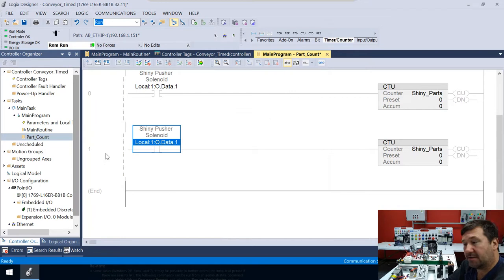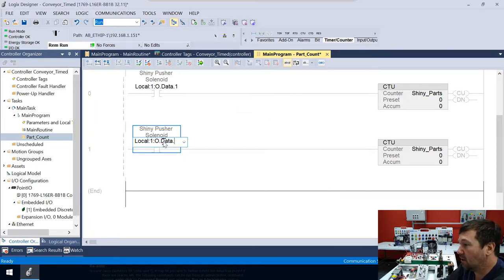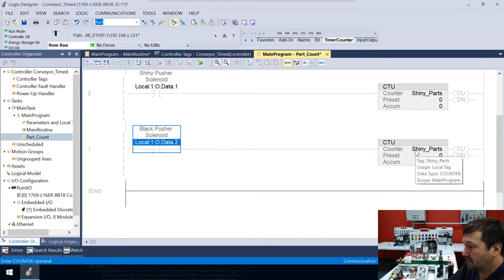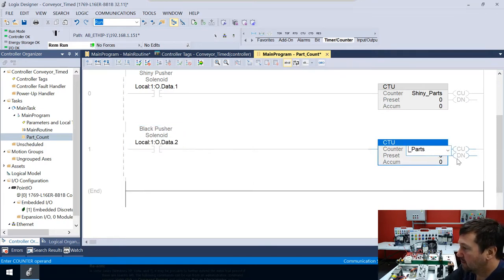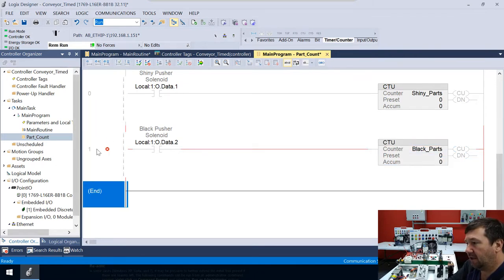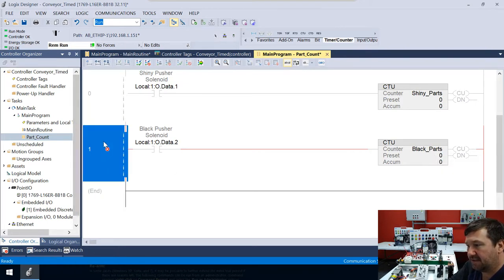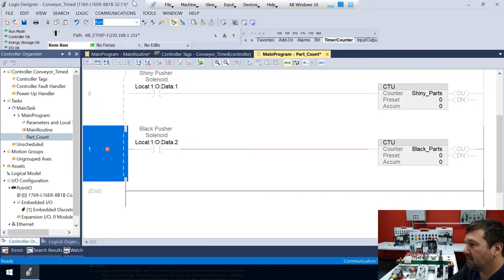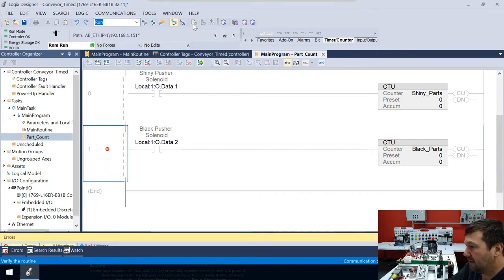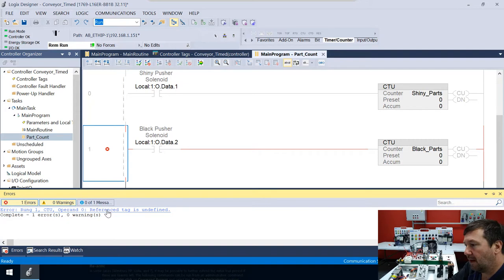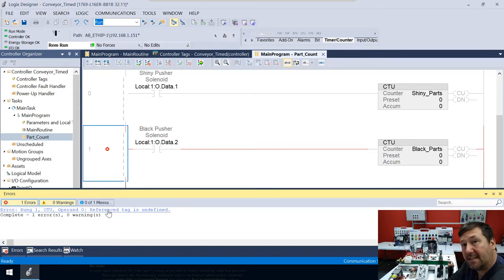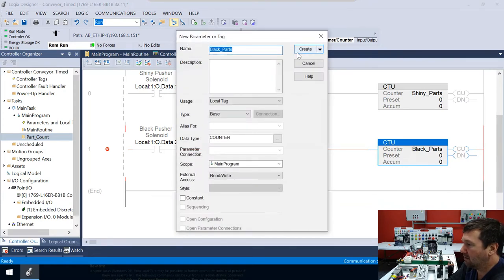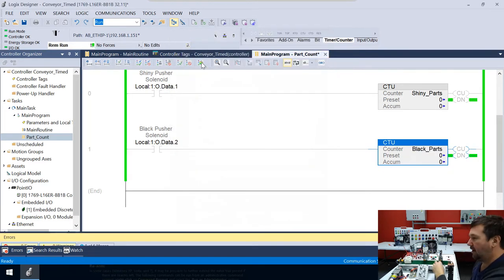So in this case, on our second rung, we want the black solenoid, which is local colon one colon O dot data dot two. And then instead of doing shiny parts, we want to count black parts. And one thing you notice, this rung looks good. This rung has a red X in it. And that's because I haven't created this yet. If you see something like this in your rung, then there's something wrong somewhere in here. Let's say we couldn't figure this out. We can hit the verify routine up here. If you drag this up, there's our errors. And it says rung one CTU operand reference tag is undefined. And if you have an undefined tag, that means it needs created. I'm going to right click here and we're going to have new black parts and it will be a counter data type. And let's go ahead and assemble that.